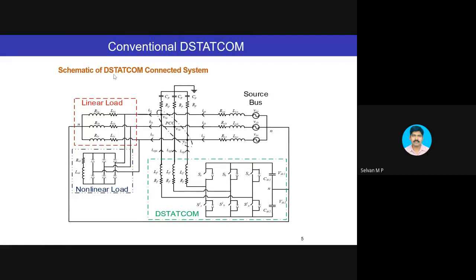STATCOM and D-STATCOM are not different in terms of functionality. Both of them are the same. The only thing is, STATCOM is used in the transmission system to control power flow in the line. This D-STATCOM is used in the distribution system to compensate the lagging power factor of the loads. Functionality wise, both are the same. Rating wise, this will be different. This will have a lower rating compared to the STATCOM which is used in the transmission system.